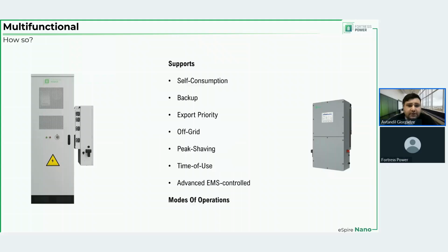What modes of operation does it support? It supports normal self-consumption. It delivers backup output, so backup applications. Export priority, in which instead of the battery and the load being the first priority, it is load and the export, and then the battery. Off-grid, you can have the system fully off-grid, and it will operate normally. It has even a configuration in the manual. You can select that this is an off-grid application, and it will not even be looking for the grid signal.